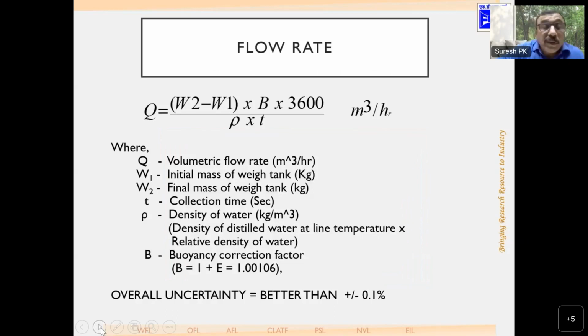Now, if you check the uncertainties, basically you are finding out the flow rate using the mass which is collected in the weighing tank, a final mass and an initial mass. The difference between the final mass and initial mass will give you the mass of fluid collected, then the buoyancy correction factor, density and time. These are the points of uncertainty involved. So as I have explained, the weighing machine calibration uncertainty affects the measurement.